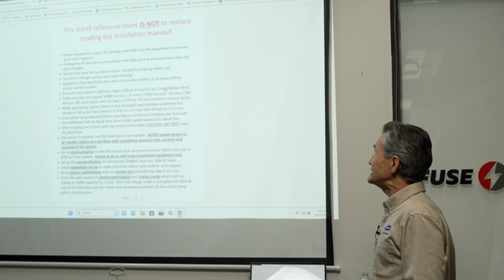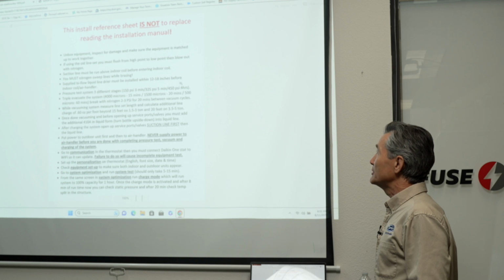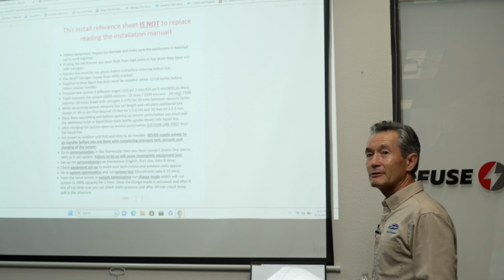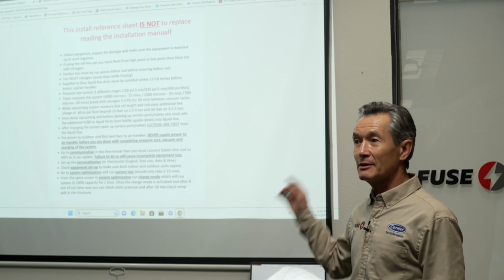And again, as you can see, the maximum pressure in here in Daikin is not 500, not 600, but 450. You have to know about that. And obviously, if you don't have proper equipment, such as a regulator for your nitrogen bottle, you have to have it for the proper PSI to be able to reach.